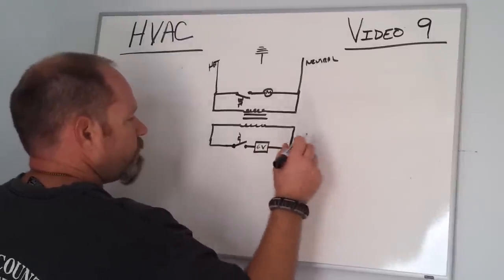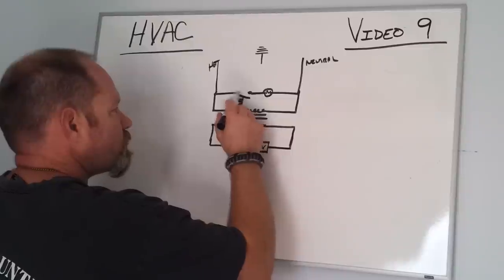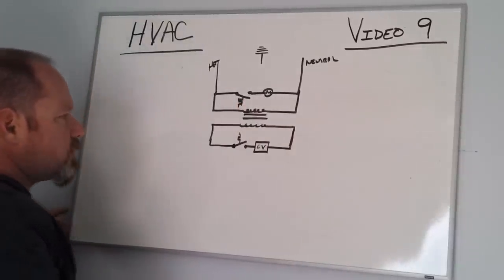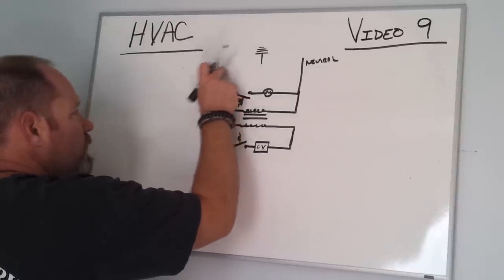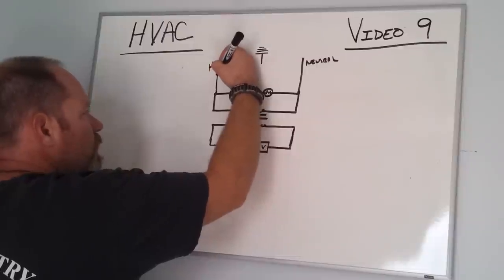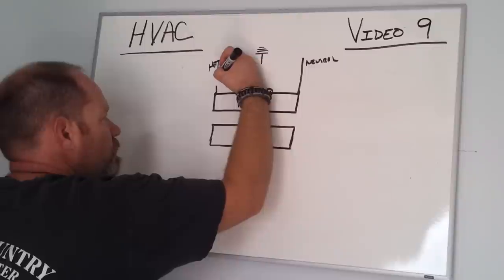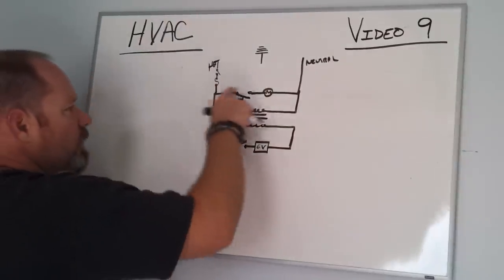Then the temperature in the furnace is rising, heats up this fan switch, which is on the high voltage side, turns the motor on. That's a pretty basic system. What we don't have installed is any type of switch. We should have an on-off or a service switch installed. And we should also have, remember, everything needs to have a fuse. We should have some type of fuse installed. Okay? So now we're protected on this side.